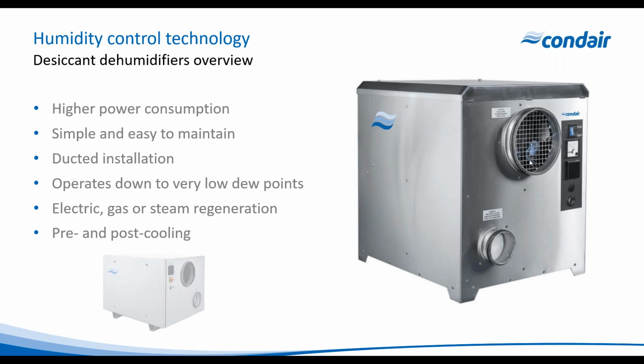There's higher power consumption for these units, and this is really because we've got that electric heater for regeneration. They're simple to maintain. Again, a filter change annually, visual inspection. You may need to change the drive belt every couple of years. And of course, they're a ducted installation. So the system has got to have supply air ducted to it and return air ducted from it. And we can, as mentioned, operate down to very low dew points.